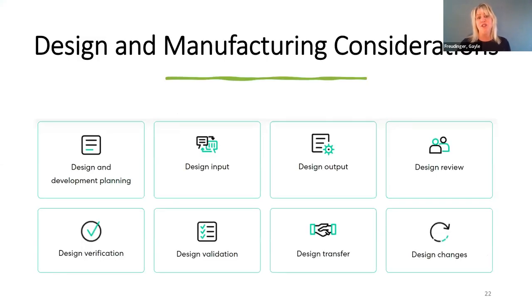Design and manufacturing considerations are one of the most critical phases for your device's success. A loosely defined and designed medical device cannot comply with the regulatory needs, and it will probably never make it to market. So you want to consider intellectual property, as I mentioned before, and starting with a prototype in most cases. Design controls are defined under the FDA 21 CFR 820.30. Information about this will be in the resources list so that you have more details.